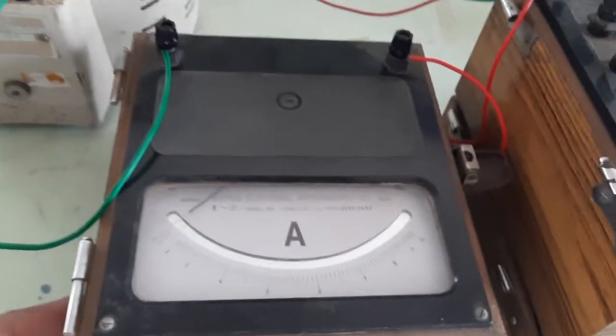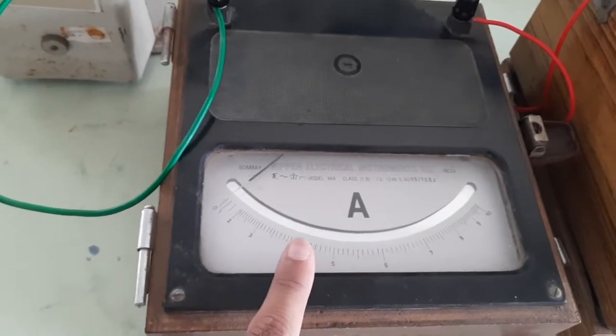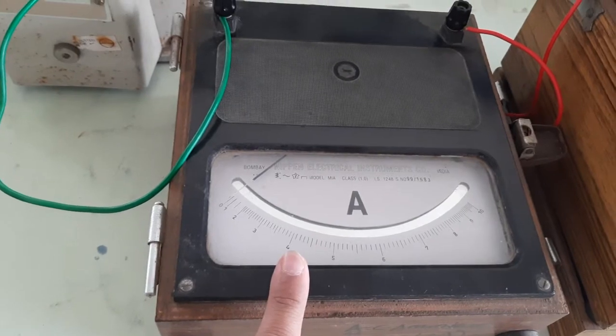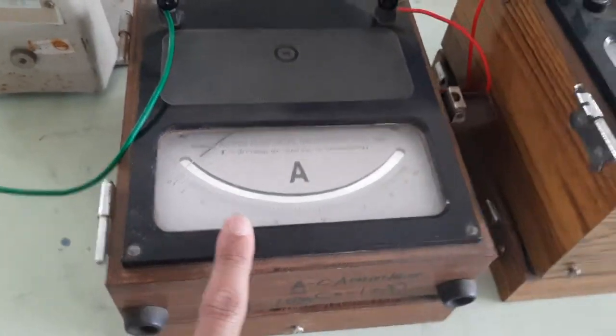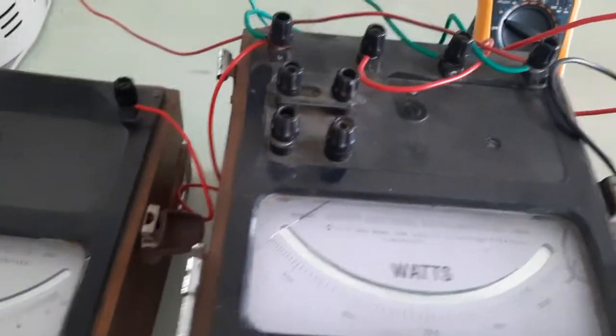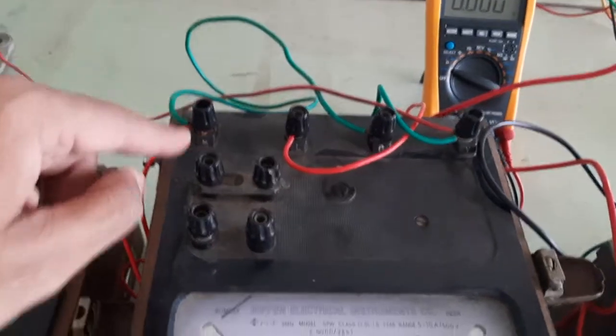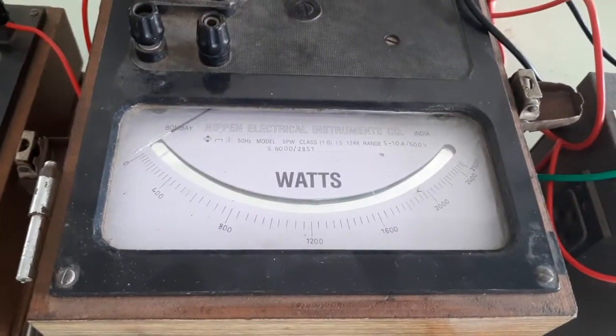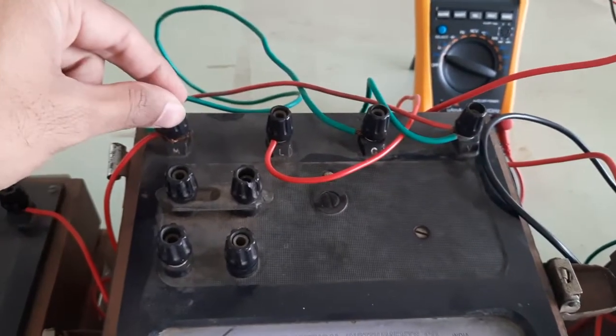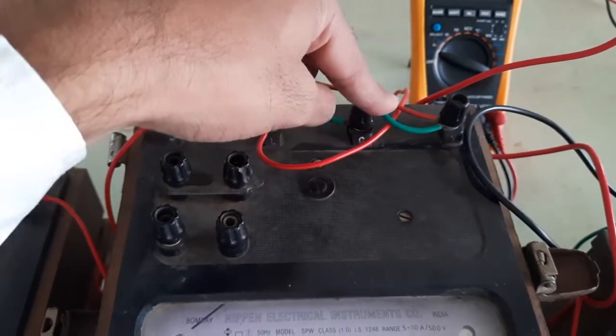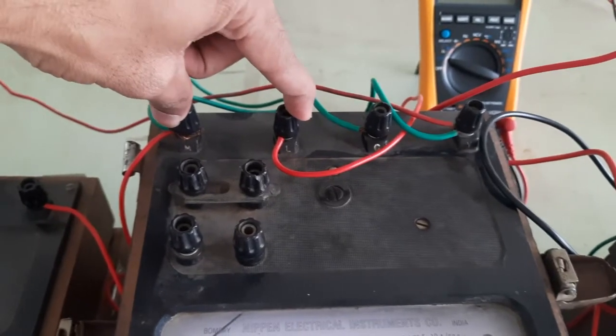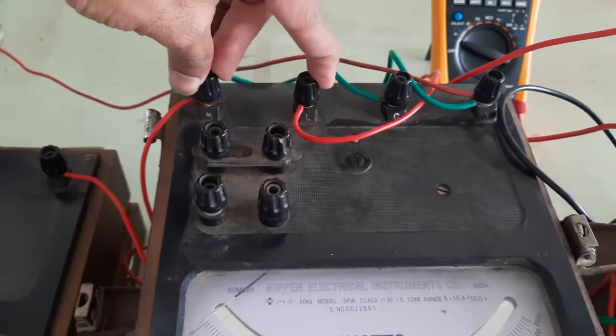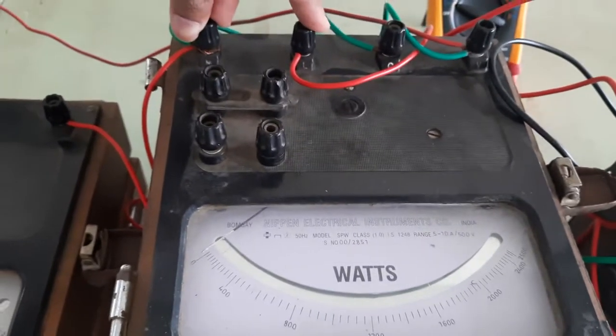Then we'll require the ammeter, from 0 to 10 ampere, which will give the reading for the primary current of the transformer. Then there is a wattmeter, which will show the reading of power in watts. There are four terminals for this wattmeter, M, L and C, V. ML will have the current coil and CV will have the potential coil, so it will measure the power directly.